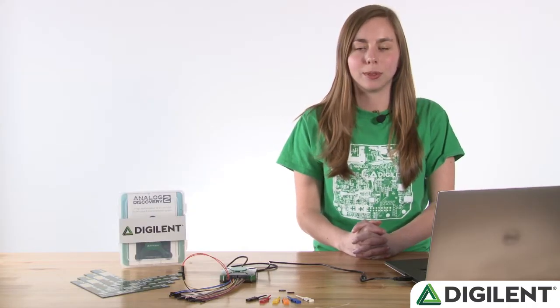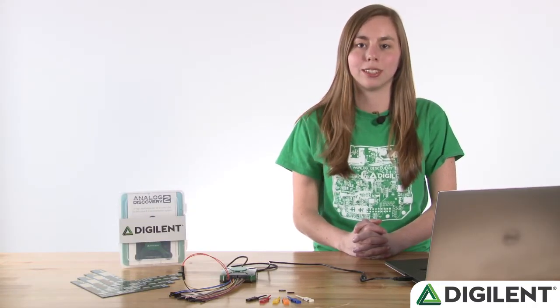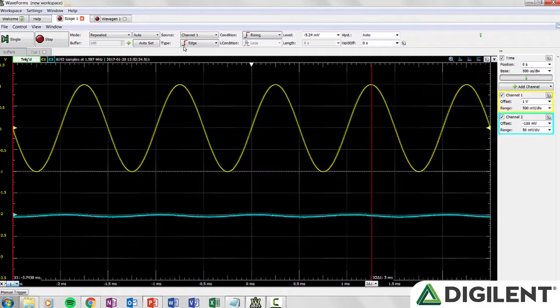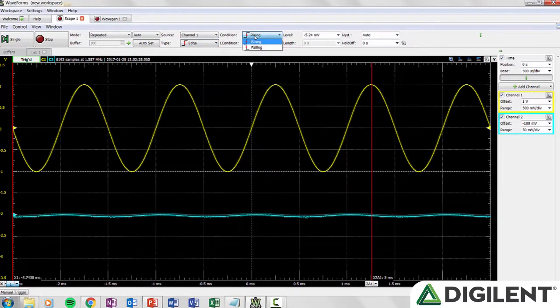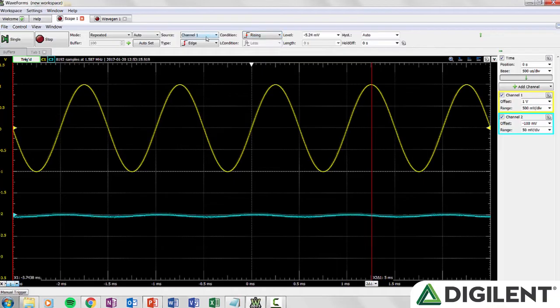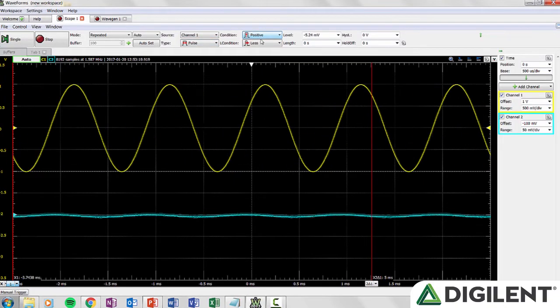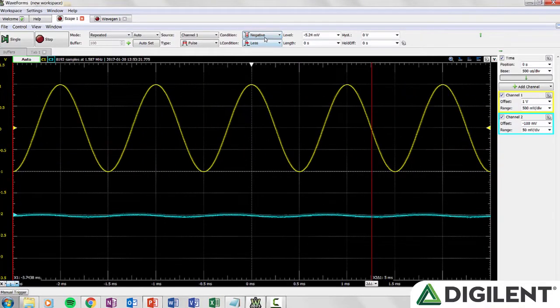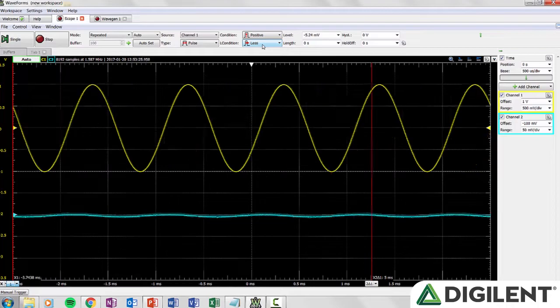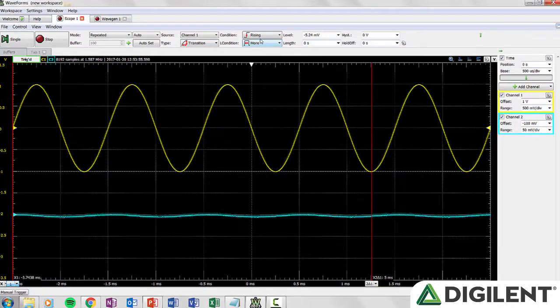Below that you can select between edge, pulse, and transition trigger types. For edge triggering you can select between rising and falling edge triggered. If the trigger type is pulse then the oscilloscope will trigger if a positive or negative pulse has a smaller or larger length than that that is set by the user. Transition is similar to pulse but the transition time of a signal is compared with a set length.